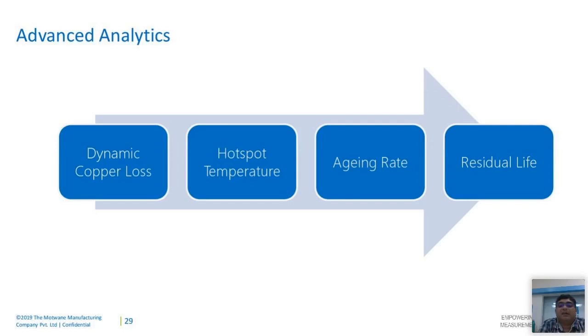Now this will help in a scenario where there are identical transformers, where one is in standby and another is operating, or both are sharing the load. Based on this kind of evaluation, it could be decided which transformer takes more loading, wherein we can reduce the losses in the windings. And this typically happens over the entire life cycle of the transformer.